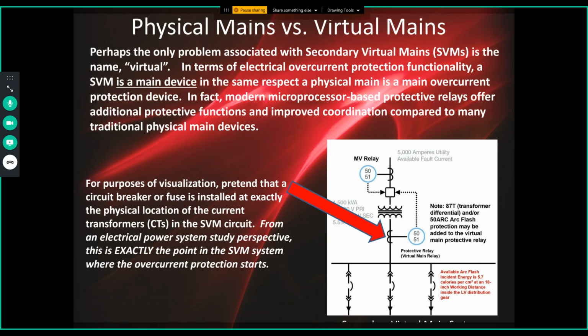And as I noted previously, if you just look at the big red arrow here, for purposes of visualization, if you remember one thing coming out of this presentation, it would be that where those CTs are located physically on the secondary bus of the transformer, that is where the overcurrent protection starts. So in terms of a power system study model, that is where you model the overcurrent protection taking place, exactly as you would if there was a secondary physical main. The only difference in this case, of course, in your power system study model, is you have to model the opening time of the primary breaker and the latency time, the assertion time of the relay itself. So those two.